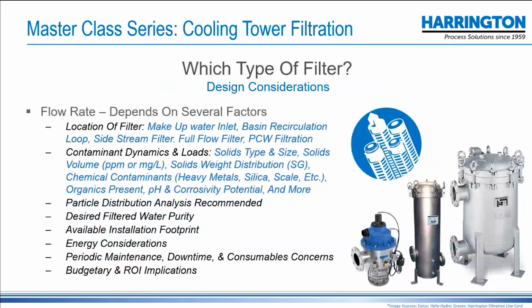So what type of filter? Well, there are so many variables that they kind of boggle the mind. But which of those 5 locations are we talking about? What is the contaminant load? What are the dynamics? What's the specific gravity of your contaminant load? What's the load and volume in parts per million, same as milligrams per liter? Any chemical constituents that you're having to deal with, corrosivity issues. If we can get some water information, we can run a Langelier index and tell you precisely how corrosive your water is going to be.